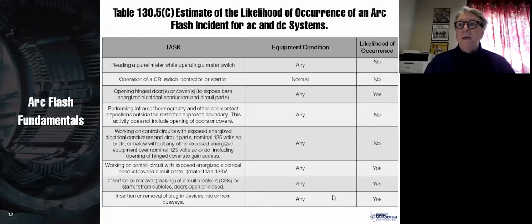Here's PPE. We always look at the estimate of likelihood of occurrence. So they always like to make this somewhat difficult. Likelihood of occurrence means if it's likely that there could be an arc flash, you have to wear your PPE. If it's unlikely that there would be an arc flash, you don't have to wear your PPE.